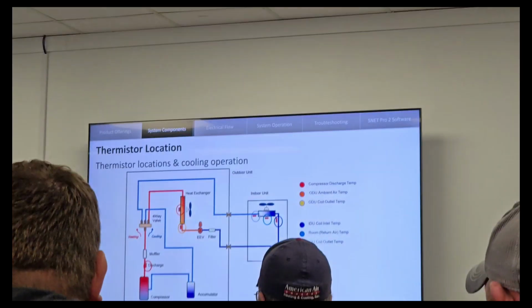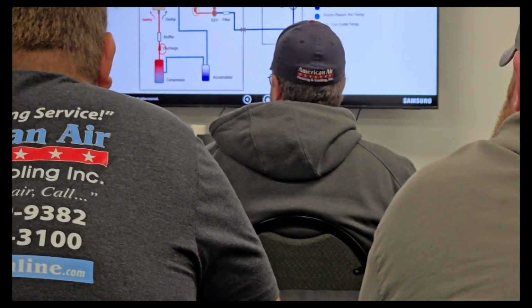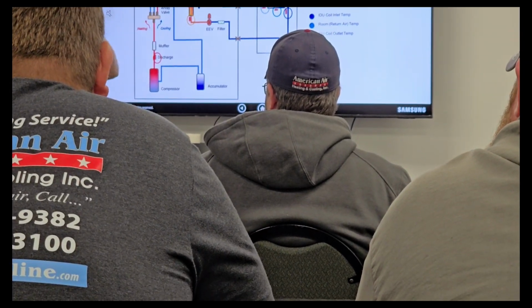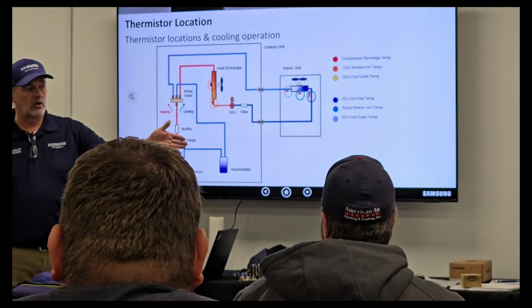So ultimately, if you ever see us do it, we'll cut that flare nut off, throw it in my bag, and take the flare nut off the outdoor units and the indoor units and use those flare nuts instead.